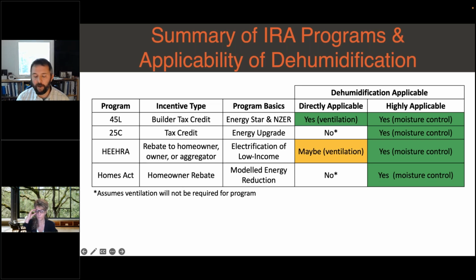Whereas on the other hand, a ventilating dehumidifier is a supply ventilation system, so it is only bringing air into the house and pressurizing the house, and then the air leaks out through various different paths. But while that air is being brought in, if the interior RH is elevated, the ventilating dehumidifier compressor will come on, and as that air is mixed in the machine and then dehumidified, it will deliver dry air and dry down the house. So the difference is basically that ventilating dehumidifiers are actively removing moisture, so they can wring out a lot of moisture, and ERVs are passively transferring the moisture, which is basically limited by physics at about 50%.